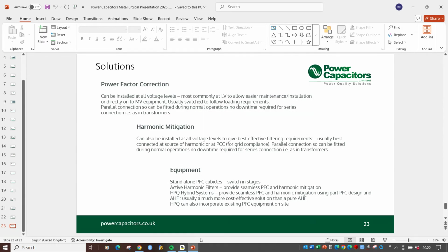It basically goes, right, you've got this much harmonic current, this much resistance on your bus bar. This is the voltage that the harmonics are going to generate. So it's the current that induces the voltage. It depends what resistance is between those two transformers. If it was as easy as that, everyone would be banging in transformers all over the place. But it doesn't.